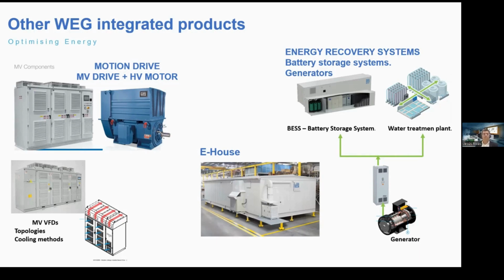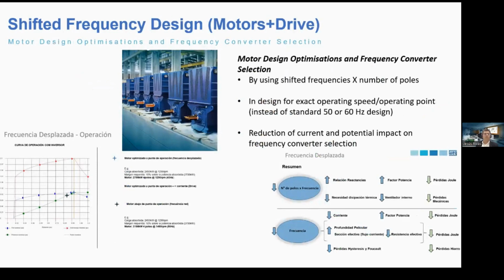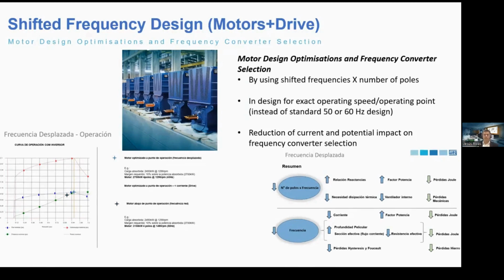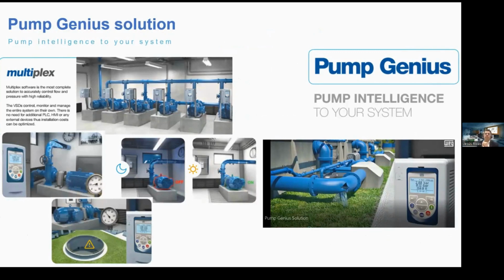We have energy recovery systems based on storage systems with batteries and generators to return energy to the desalination plant. Optimization in motor and drive by designing with a variable frequency concept. When we design the motors with a drive and we put this at the exact rotating speed for the operating point, instead of the standard 50 Hz or 60 Hz, whatever, you are reducing a lot the size of the motor, consequently the price, and you avoid the impacts on the current to calculate the frequency converter. So you don't have to rise too much. Here in the curves, well, this is more specific details, but with this definition, you go to the required proper point, okay? We have other solutions, the Pump Genius solution, which is a special function that turns your standard frequency converter, your standard drive, into a controller for the pumping system.